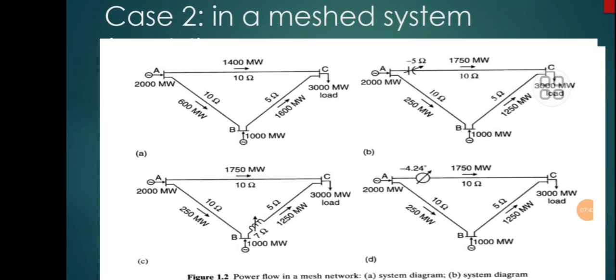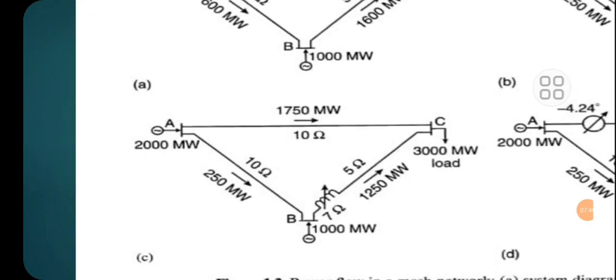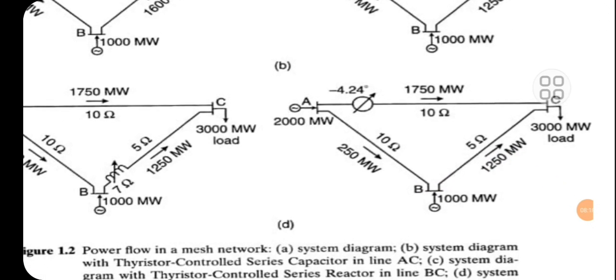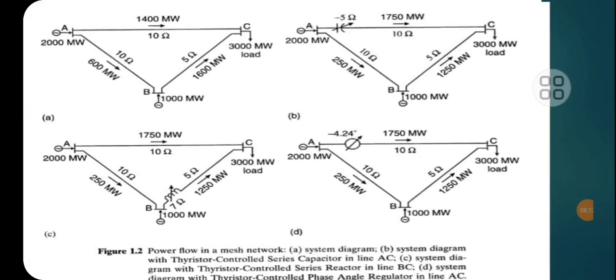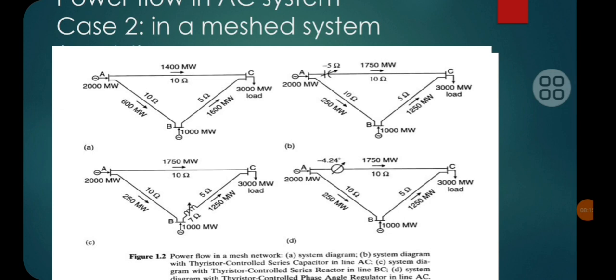So the same powers can be achieved in another way, but that is by making a change in line BC by putting a reactor in series with the transmission line BC of 7 ohms impedance. Consequently, the impedance of the transmission line BC will change to 12 ohms, and here again you will get 1250 megawatts flowing through the transmission line BC. The same values can be obtained by inserting a phase angle regulator in line AC. So in this manner, power flow control is possible by placing a reactor or a capacitor or a phase angle regulator.